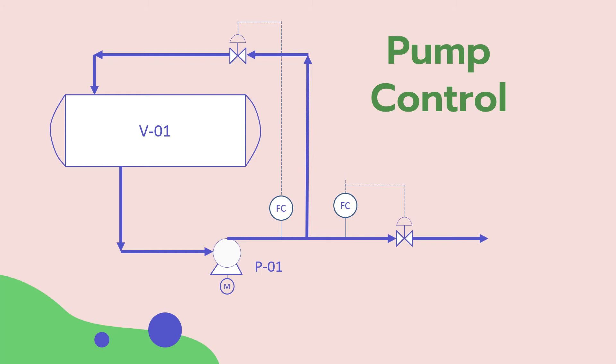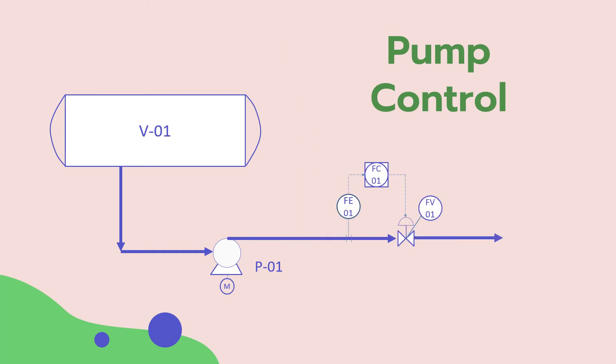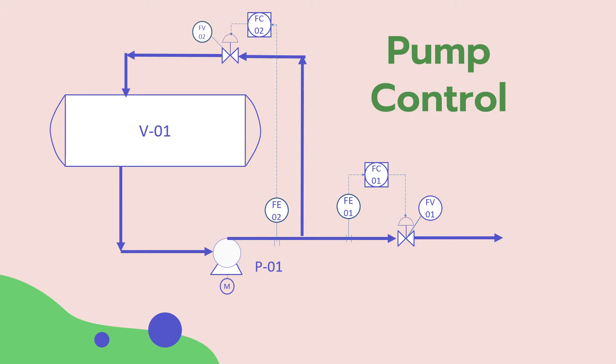Let's assume that we shall choose this control scheme. But this control scheme is so simplified — we need to show our instrument engineer exactly what is required. So we need to show more details instead of this FC. We need to show the flow device that sends a signal to the controller through a cable, which is FE. The square around the circle in the FC here means that its reading is shown to the operator in the control room. And the control valve will be called FV. We also would add tags, so each instrument or valve will have a unique tag to be easily tracked.